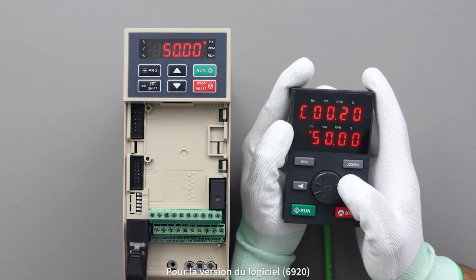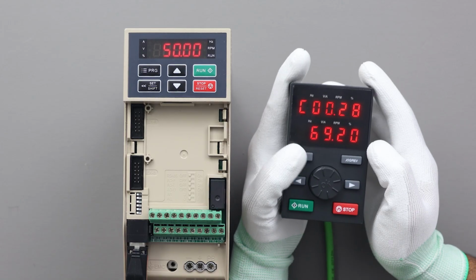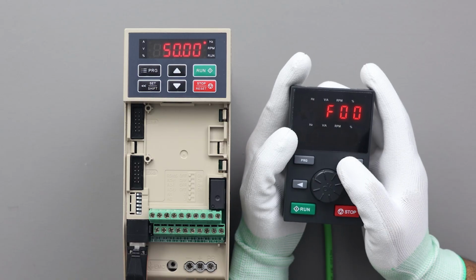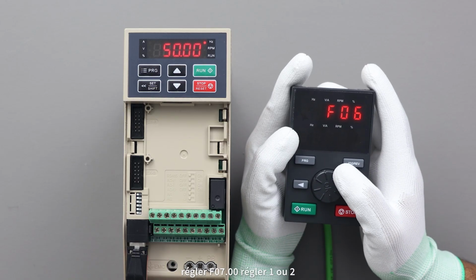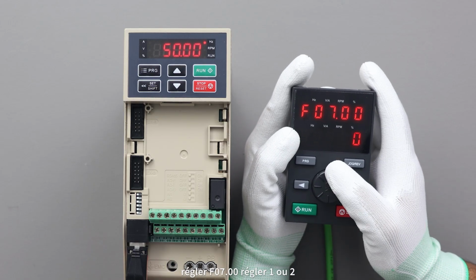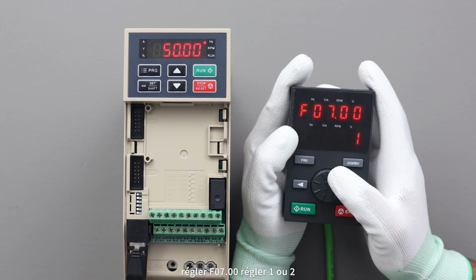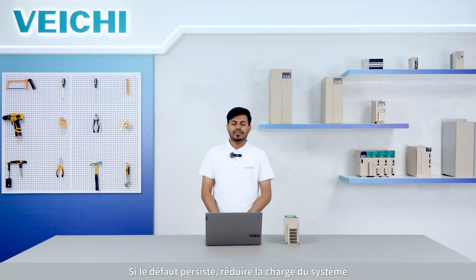For software version 6920, set F07.00, set 1 or 2. If fault still persists, reduce load on the system, or you can select a bigger capacity drive or connect a braking unit.